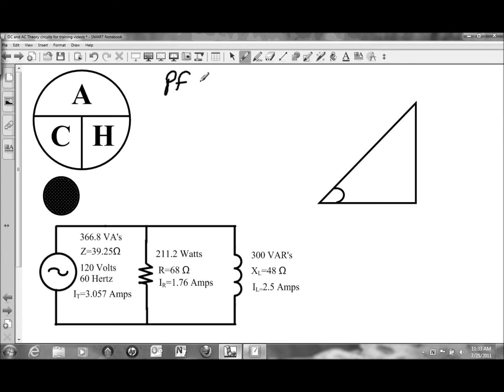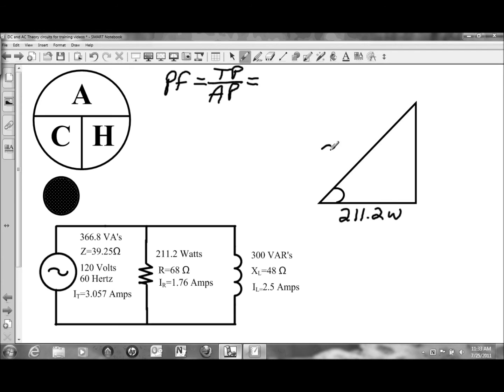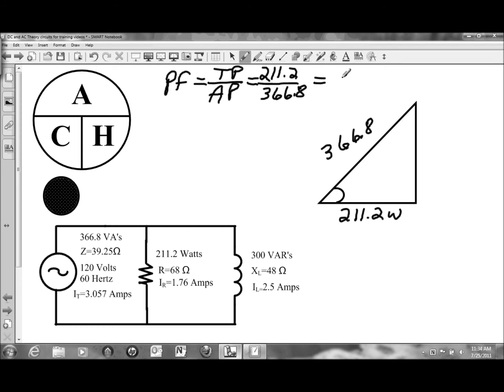Power factor is a ratio of true power to apparent power, or wattage to volt-amps. Looking at the two different sides of the triangle, we have 211.2 watts as our true power, and the apparent power is 366.8 volt-amps. That ratio for power factor will be 211.2 divided by 366.8, which gives us a power factor of 57.5%.